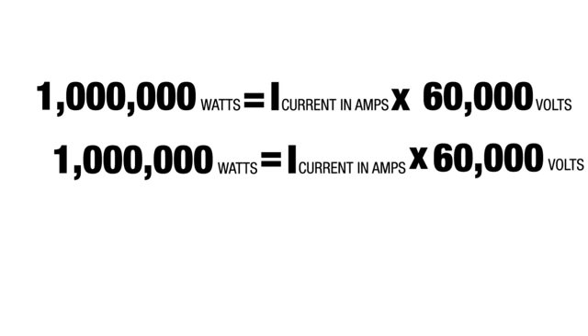Let's do 1,000,000 watts at 60,000 volts. Now, what's the new amperage going to be? So to figure out the new amperage, we'll divide both sides by 60,000 and we'll find out that the new amperage is about 16.7. Perfect. So what we'll do is we'll just run 60,000 volts at 16.7 amps. That works out. So we can just run the 60,000 volts right to the outlet.